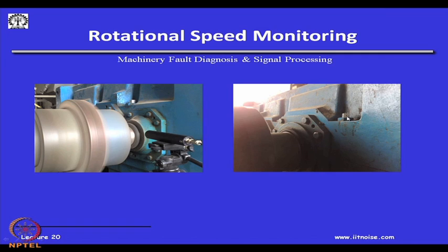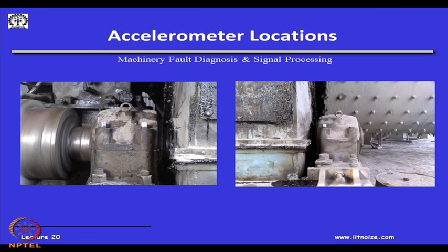And if you will see a couple of holes here, one hole here and the stud coming out on this accelerometer block, we can either screw on the accelerometer to measure the acceleration. I will show you another view. This is how dirty or unhealthy the conditions are in the actual industry, with gears everywhere and grease everywhere. There is no space, and these are always rotating, the plant would not shut down. So, what we have done is glued these mounting blocks. We just clean the surface, remove the grease, put a cement, and then it sticks, almost instant glue, and then you can put this block onto this block and screw on the accelerometer.